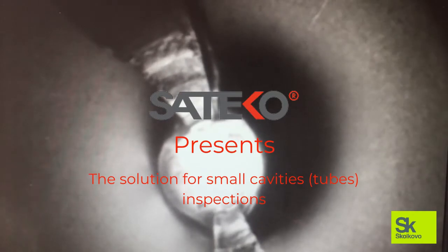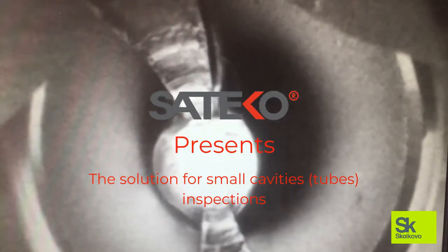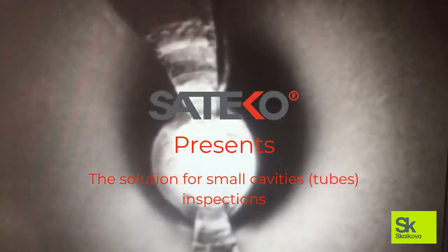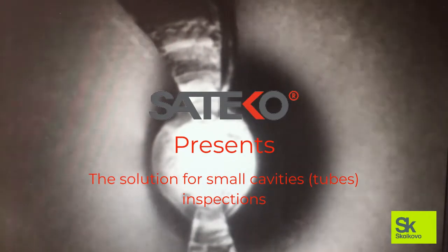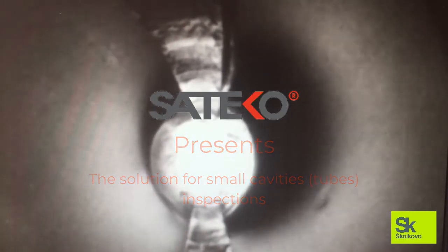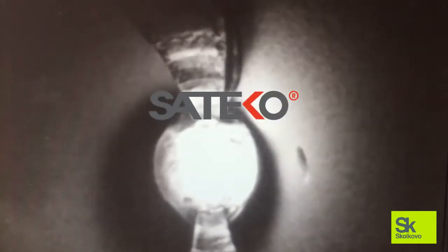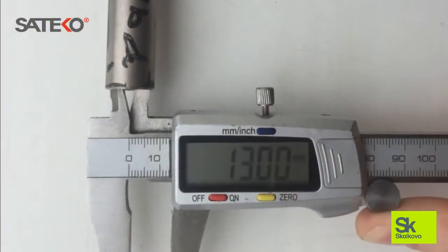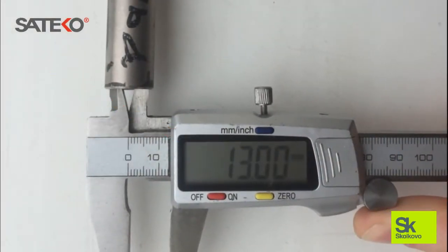This is a rather specific solution designed to inspect cavities of small diameters with a high level of reflection from the inner surface. As a rule, these are pipes of small diameters. For example, the inner diameter of the pipe that we examined in the test video is 13 mm. The maximum pipe inner diameter for this solution is 50 mm. But if you need a solution for a larger or smaller diameter, we will be ready to develop it up to your requirements.